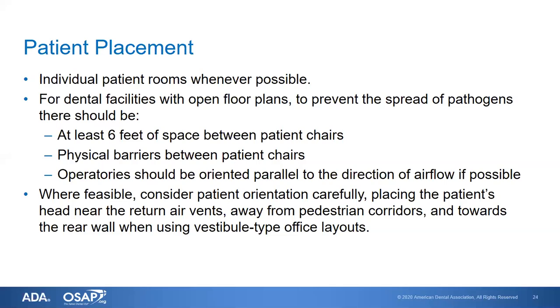If barriers go all the way to the ceiling, you could interfere with the airflow in the space. Make sure you're not blocking vents or creating a setting with no airflow in the patient care area. If possible, orient your operatories parallel to the direction of airflow. Consider patient orientation carefully — you can place the patient's head near return air vents, or prioritize chairs near return air vents for aerosol-generating procedures. Also orient the patient's head away from pedestrian corridors and towards the rear wall so that aerosol-generating procedures are contained within that space.